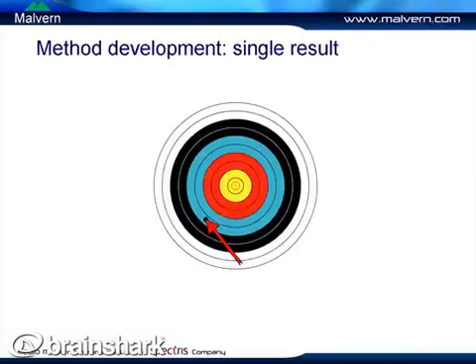Looking at a single result, we can see that one result is not really sufficient information to tell us much about the precision of our measurement. If we get only one result, we don't know how precise it is, and we can't look at accuracy either because we can't examine its deviation from the mean. In particle sizing, it's also extremely important to make more than one measurement in order to assess the stability of your sample in whatever dispersion you're measuring.